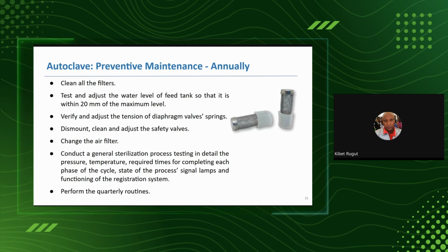The valves that close and open, the release valve and the relief valves, it is good to feel whether they are tensioning well and sitting back in their natural seats. For safety valves, which is an annual event, it is good to dismount, clean, and adjust, but not without the maintenance manual, please, because every manufacturer usually has its own methods of dismantling. They are not all the same. They can be mounted differently.